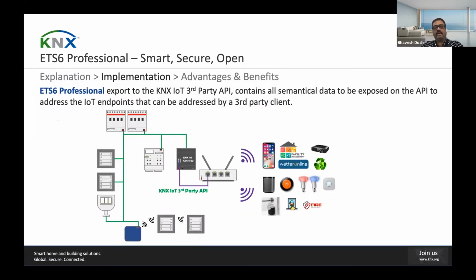So an exported IoT project has all the necessary information that needs to be passed to a KNX IoT third-party API so that a KNX installation can be interoperable with any third-party client, which will exchange information with the building. Example, a weather forecast API service could inform the building about upcoming sunshine so that the building can then self-adjust the energy consumption and switch its electricity source from grid to the batteries or its solar panel system.